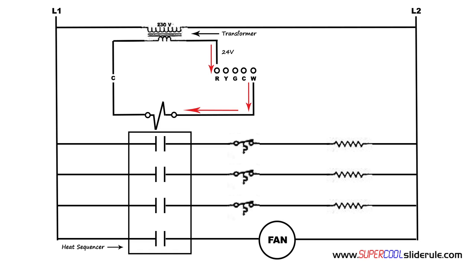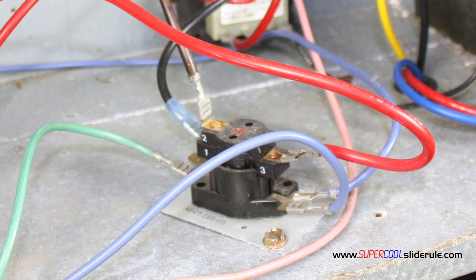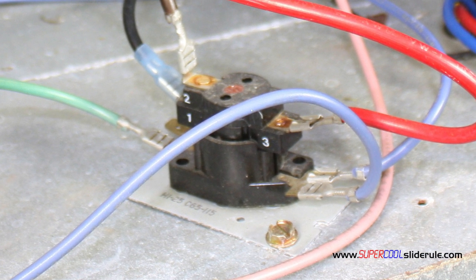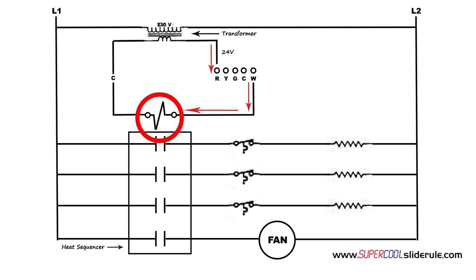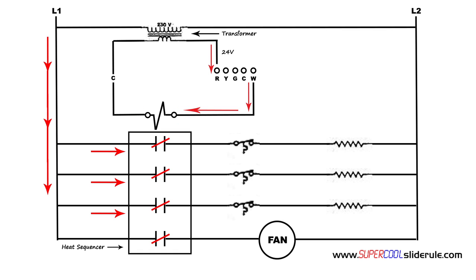The low voltage is connected to the coil of the heat sequencer or relay. The coil in this application is located on the bottom terminals located here. When this coil is supplied with low voltage, it causes the contacts to close, allowing electricity to flow through it.